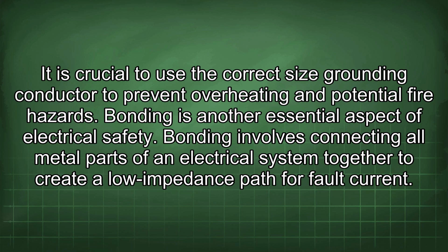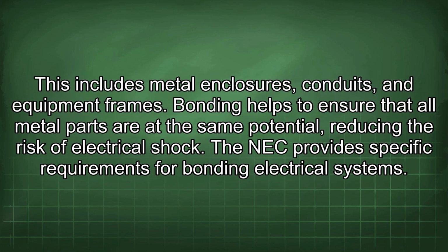Bonding is another essential aspect of electrical safety. Bonding involves connecting all metal parts of an electrical system together to create a low impedance path for fault current. This includes metal enclosures, conduits, and equipment frames. Bonding helps to ensure that all metal parts are at the same potential, reducing the risk of electrical shock.